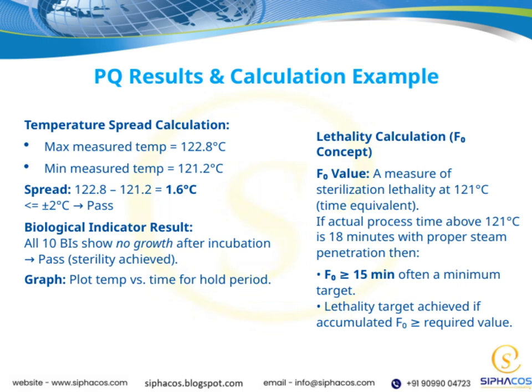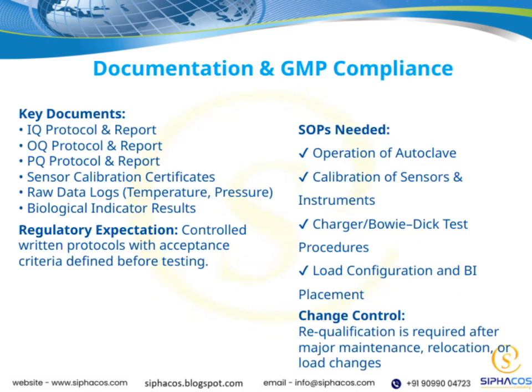Next, the biological indicator results. All 10 biological indicators showed no growth after incubation, which confirms that sterility has been successfully achieved. Finally, there's a graph showing temperature versus time during the hold period. This visual helps us verify that the process maintained the necessary conditions for the required duration, ensuring effective sterilization. In summary, these calculations and results collectively confirm that the sterilization process met both the temperature and biological criteria for effective sterilization. Let's take a closer look at the key documents involved in this process.